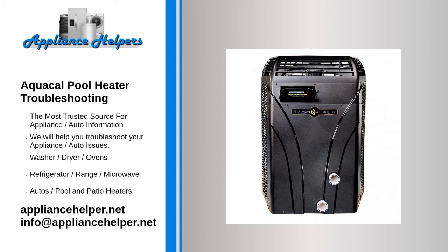Check the temperature settings. Most pool heaters are incredibly temperamental when it comes to the temperature you set it at and the outdoor temperature. If your pool heater is not set to a high enough temperature, then it may not appear to be working, though it's working just fine. Ensure that the pool heater's thermostat has a higher temperature setting than the current water temperature of your pool. This way, the water being pumped in is actually warmer.